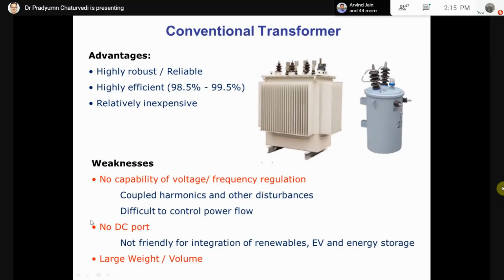Now the need is that you have to interconnect your PV, wind, or other DC sources with the existing grid. You cannot replace the whole existing grid with a new DC grid as the scenario is changing. To address this, there are no DC ports available in this transformer, no DC port available. So where you have to connect this PV, wind or fuel cell battery, you ultimately have to develop some DC port or DC bus, a common DC bus at different DC voltage levels. So this is not friendly for integration of RES, EV, and storage.